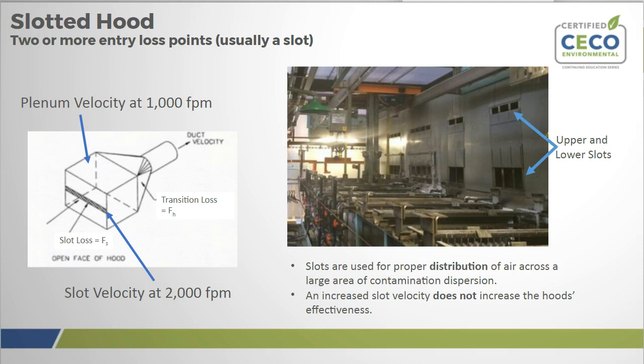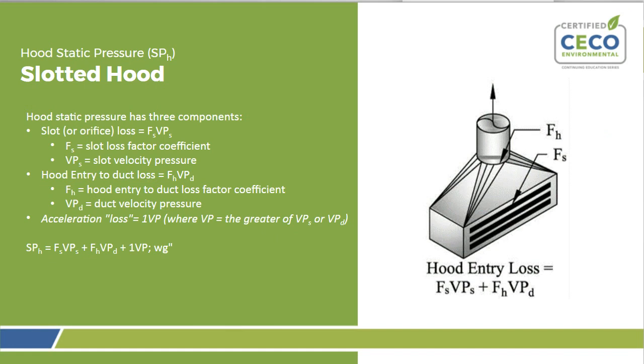Knowing that a slotted hood has two loss points, it is possible to calculate the static pressure. Along with those hood losses, the slot loss and the transition loss, we have to incorporate the acceleration loss in order to have the overall static pressure required at that hood. And so we're going to add the hood entry losses. For this slotted hood, there are two components for the hood entry loss, and to that we have to add our acceleration loss. That acceleration loss is sometimes termed the Bernoulli coefficient, and that is the amount of energy required to get the mass of air to the velocity that we need.